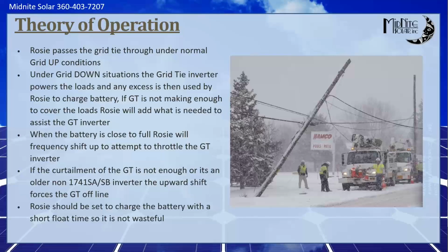So I'm going to try to wrap up with the theory of operation and how to test this. So we've sort of talked about the theory of operation, but essentially under normal conditions, the Rosie closes its relay and it just looks like it's not even there. The grid tie inverter sells to the grid, everybody's happy, everything's doing what it's supposed to do. But when the grid is down, when the telephone pole looks like that and the power is off, then the grid tie inverter, the Rosie stays on, it opens its relay, the grid tie inverter then is fooled into thinking the grid is there, and it helps maintain the loads, charge the battery. If the GT inverter is not making enough to cover the loads, the Rosie will add what's needed.